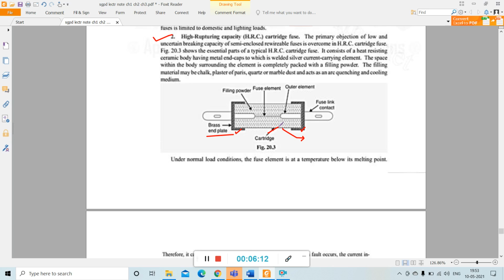So it consists of a heat resisting ceramic body having metal end caps to which is welded the silver current carrying element. Inside this, here the fuse element is welded. The space within the body surrounding the element, that means this is the space surrounding the element, is completely packed with a filling powder. This is the filling powder over here. The filling material may be chalk, plaster of Paris, quartz, or marble dust, and these act as an arc quenching and cooling medium. So how does it operate?